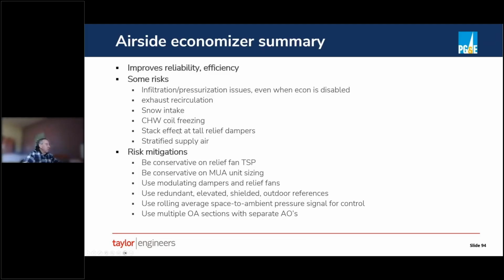One curious issue that we saw, we didn't expect, is that one data center was trying to use barometric relief only for economizer relief, and that meant really big dampers. And those dampers were so tall that there was actually a stack effect where the hot exhaust air was going out the top of the damper at the same time that cold air was being drawn in at the bottom of the damper. So the space was positively pressurized, but we were still getting infiltration through the damper. And stratification of supply air, again, organizing and orienting your dampers is really key. These can all be mitigated. And basically here's sort of how to do that.